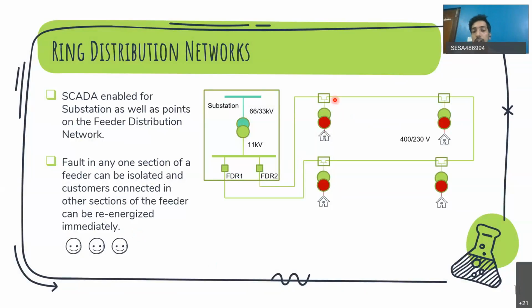That could be done with the help of a particular piece of equipment that people could install in the field, in the distribution network outside the substation. With that, SCADA was enabled not only for the substation equipment, but also for some of the equipment in this new device. One big advantage is that a fault in any one section of a feeder can be isolated, and customers connected in other sections can be re-energized immediately. If there is a fault in this section, with the help of this new equipment you could just isolate this particular section and immediately restore supply to the other customers, so that they are not under any outage. That is a big plus.